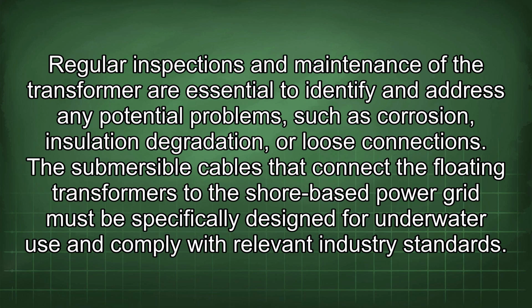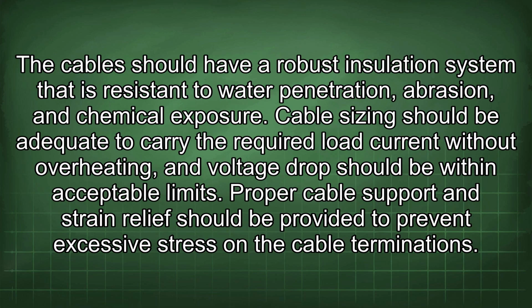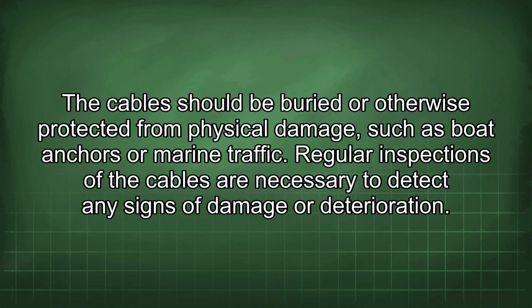Regular inspections and maintenance of the transformer are essential to identify and address any potential problems such as corrosion, insulation degradation, or loose connections. The submersible cables that connect the floating transformers to the shore-based power grid must be specifically designed for underwater use and comply with relevant industry standards. The cable should have a robust insulation system that is resistant to water penetration, abrasion, and chemical exposure. Cable sizing should be adequate to carry the required load current without overheating, and voltage drop should be within acceptable limits. Proper cable support and strain relief should be provided to prevent excessive stress on the cable terminations. The cable should be buried or otherwise protected from physical damage, such as boat anchors or marine traffic. Regular inspections of the cables are necessary to detect any signs of damage or deterioration.